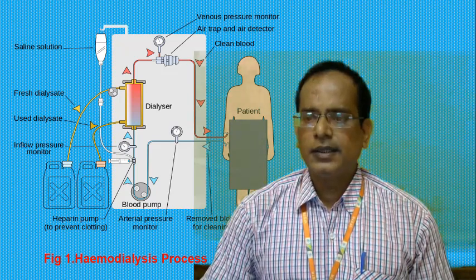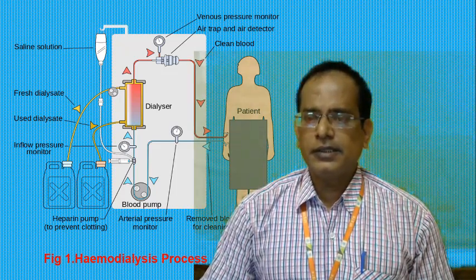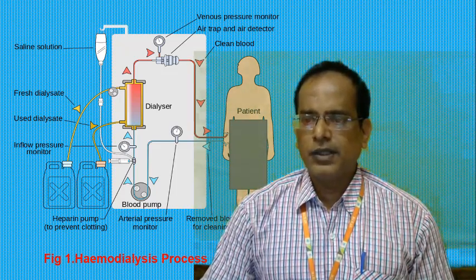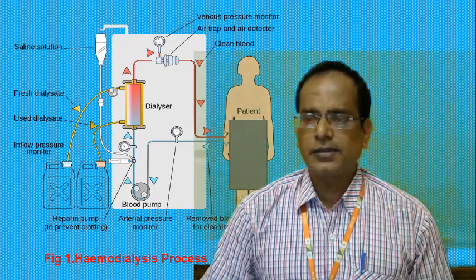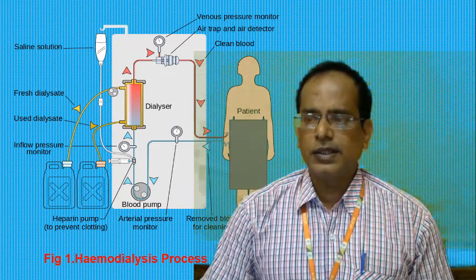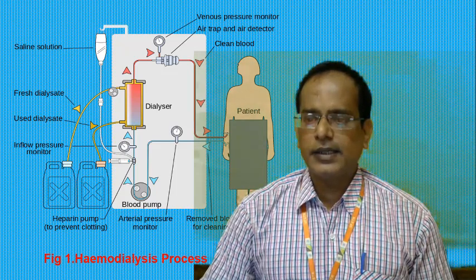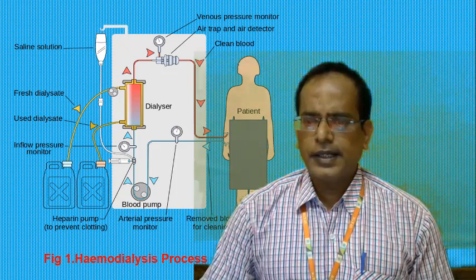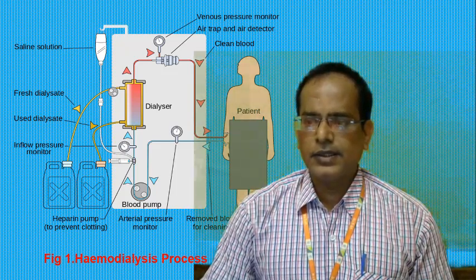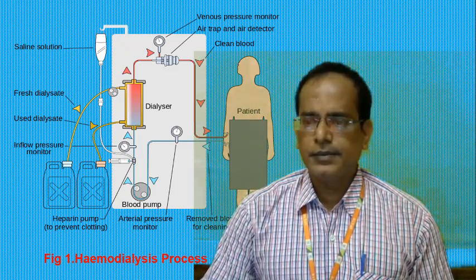The dialyser machine filters blood during the dialysis process. Blood enters the machine from the body under pressure from a radial artery, and is then sent to a roller pump — also called a peristaltic pump — which controls the pressure and flow rate.